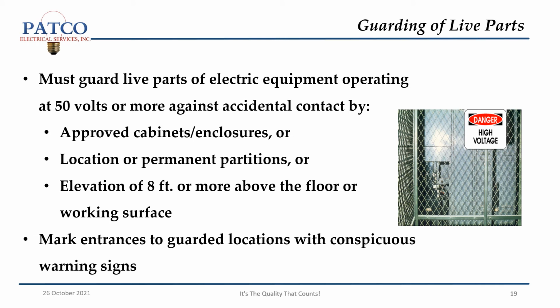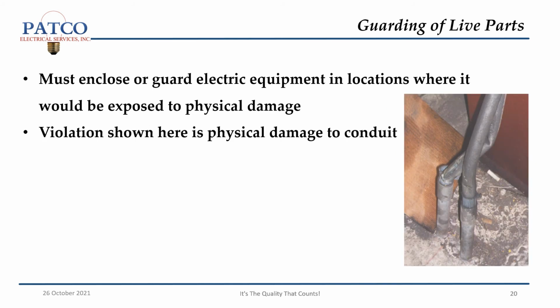Guarding of live parts. You must guard live parts of electrical equipment operating at 50 volts or more against accidental contact by approved cabinets, enclosures, or location or permanent partitions, or elevation of 8 feet or more above the floor working surface. Mark entrances to guarded locations with conspicuous warning signs. You must enclose or guard electrical equipment in locations where it would be exposed to physical damage. The violation shown here is physical damage to the conduit.